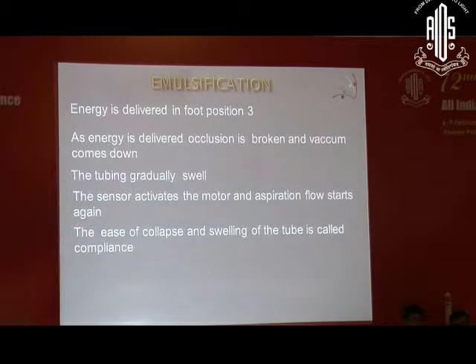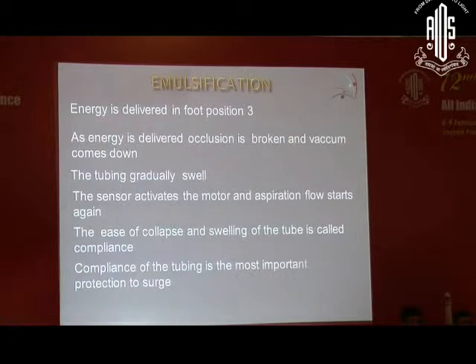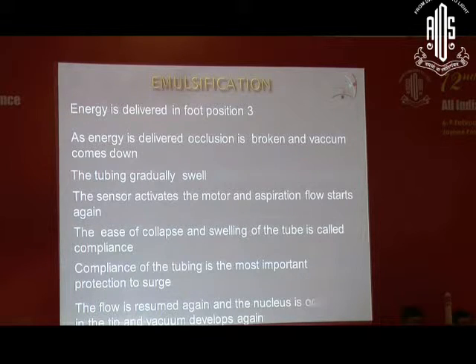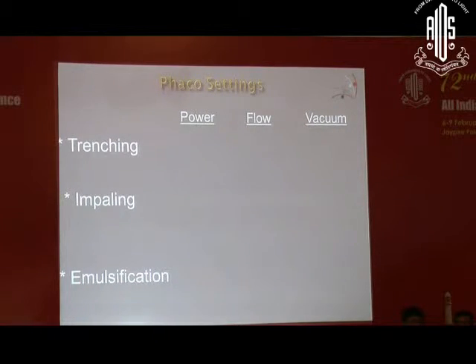So the ease of collapse and swelling of the tube is called the compliance. The newer machines have better compliance or use less compliant tubing, so surge is minimized. They use stronger motors also. The compliance of the tubing is the most important thing that protects against surge. When the flow is resumed, the whole cycle repeats, the nucleus is occluded in the tip and the vacuum develops again. So this is the cycle which keeps on repeating again and again.